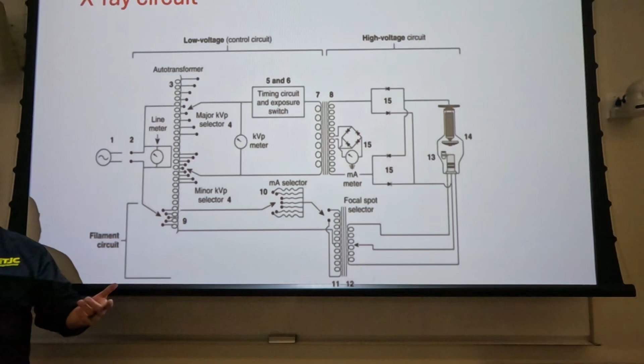So we want the kVp to be predictable by the time we get it to the auto transformer. And that's the purpose for line compensation. Now you're going to run into questions on tests that ask just that: what makes sure that the voltage is accurate before it gets into the auto transformer? That's line voltage compensation. You may even see questions that ask something to the effect of what is the one control that you don't see on your control panel. Well, the machine takes care of itself.